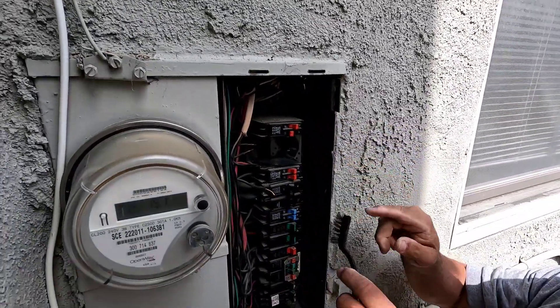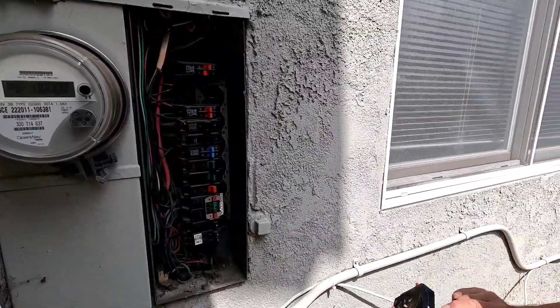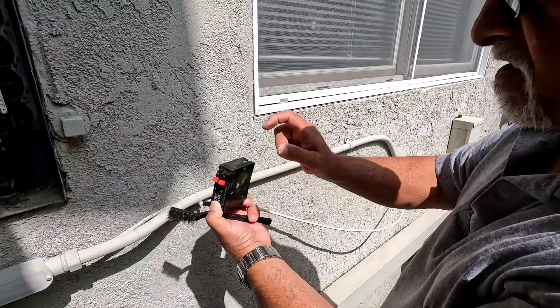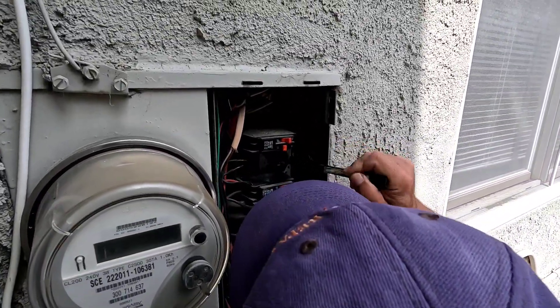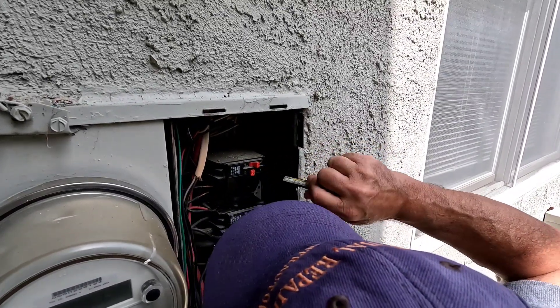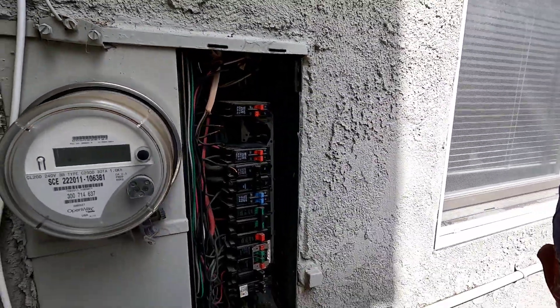The reason why we're cleaning the top of that off is because it gets a little sketchy with these when they're arcing. But obviously they've been arcing on the sides, not here, which is good news. But it doesn't hurt to make sure because I can't see exactly on top of it. The other breakers look good — they look healthy.